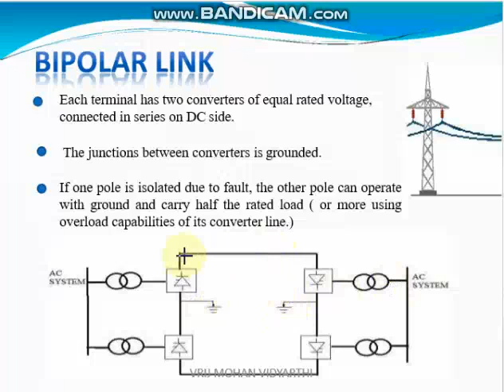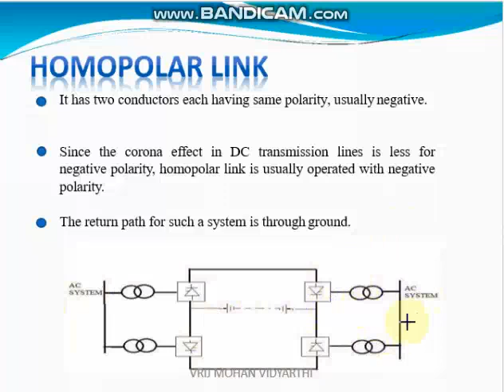That is a homopolar link. It has two conductors, each having the same polarity, usually negative. Since the corona effect in DC transmission is less for negative polarity, the homopolar link is usually operated with negative polarity. The return path of such a system is through the ground. This is the diagram for the homopolar link, and this is the ground. We are using negative polarity.